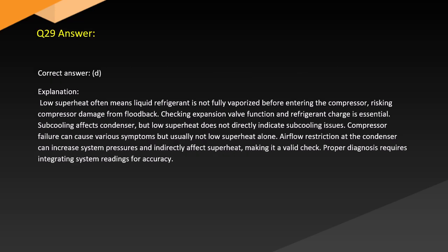Answer. Correct answer, D. Explanation. Low superheat often means liquid refrigerant is not fully vaporized before entering the compressor, risking compressor damage from floodback. Checking expansion valve function and refrigerant charge is essential. Subcooling affects the condenser, but low superheat does not directly indicate subcooling issues. Compressor failure can cause various symptoms, but usually not low superheat alone. Airflow restriction at the condenser can increase system pressures and indirectly affect superheat, making it a valid check. Proper diagnosis requires integrating system readings for accuracy.